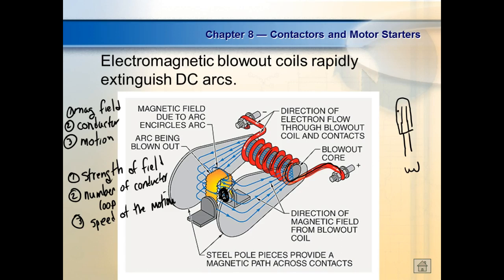So what happens is the contacts close. We come up here and put a magnetic field in here. This is going to concentrate up these plates. The magnetic field is going to shoot through the gap, and it's going to basically blow the arc out, right? Okay, so that's when it closes. So these guys help blow out the arc when it closes, which is not the big thing.